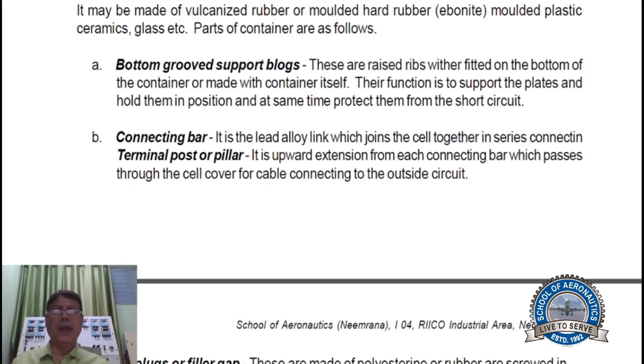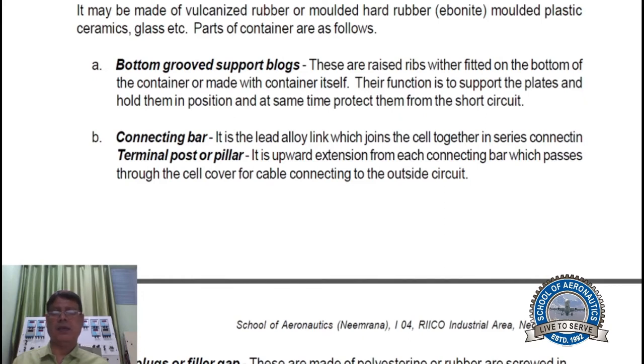Their function is to support the plates and hold them in position, and at the same time protect them from short circuit. Connecting bar — it is a lead alloy link which joins the cells together in series connection. Terminal post or pillar — it is an upward extension from each connecting bar which passes through the cell cover for cable connecting to the outside circuit.